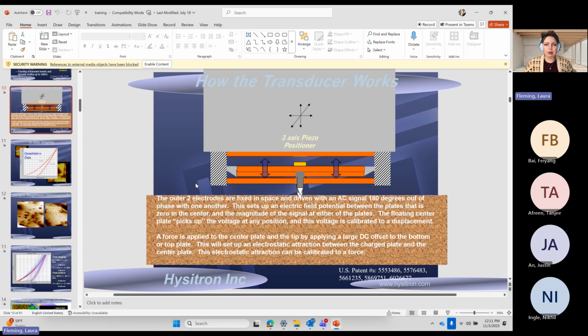So it works because the outer 2 electrodes are fixed. To measure displacement, we have an oscillating AC signal that's 180 degrees out of phase. As the plate moves through space, it works like an antenna, basically, through an electric field. So as it moves, there is a relationship called our displacement scale factor between how far it moves and what that displacement actually means. So that's how that calculation is done.